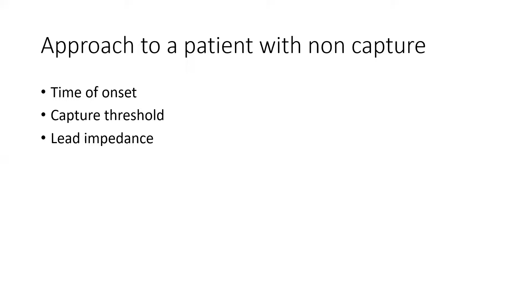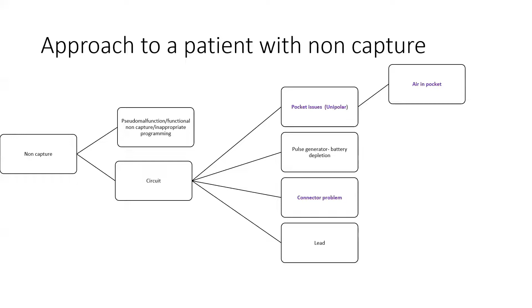After ruling out pseudo malfunction, the search for etiology may be directed to individual components of the entire circuit. These may be pocket issues, pulse generator issues, a connector problem, or lead issues. Now, pocket issues are particularly important in unipolar pacemaker, which was the case with our patient. For example, a unipolar pacemaker will not pace till it is placed in the pocket, or presence of air, for example, in subcutaneous emphysema in the pocket, may be responsible for loss of anodal contact in case of unipolar pacing. So in such cases, you can press down the pacemaker so that it comes in contact with the muscle and you will regain pacing.